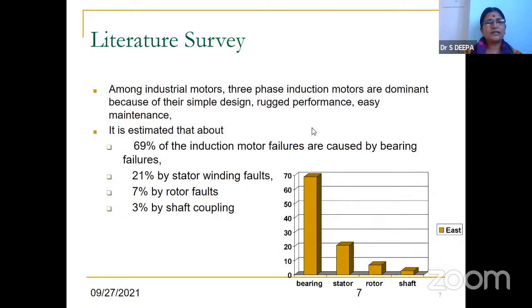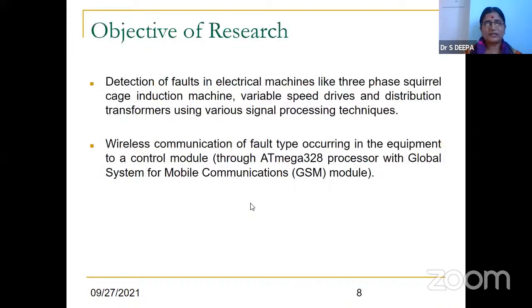In the literature survey, we see that among industrial motors, three-phase induction motors are dominant because of their simple design, rugged performance, and easy maintenance. It is estimated that about 69% of induction motor failures are caused by bearing failures, 21% by stator winding faults, 7% by rotor faults, and 3% by shaft coupling. These are the different types of faults and what the literature says. So what is the objective of the research? Detection of faults in electrical machines like three-phase squirrel cage induction machines, variable speed drives, and distribution transformers using various signal processing techniques.